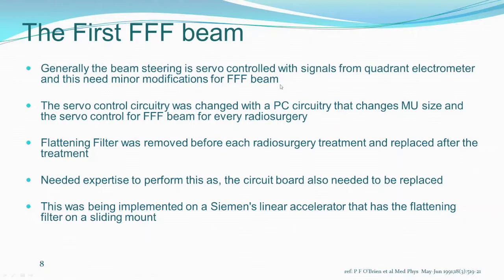So they had to do two electronic changes. One was that the servo control circuitry had to be changed, and the PC circuitry had to be changed for the MU size, the monitor size of the MU, that is the dose per MU. And this dose per MU and the servo control, for FFF beam, for every radiosurgery, they had to change when they removed the flattening filter. When they put back the flattening filter, the circuitry board was removed.